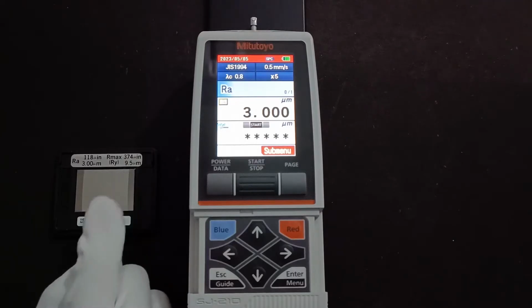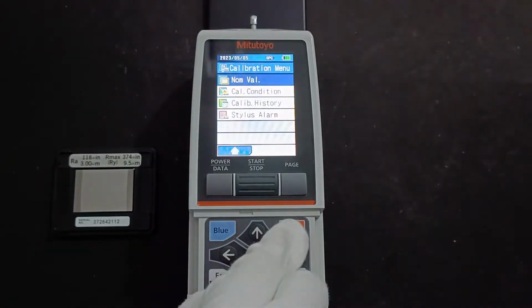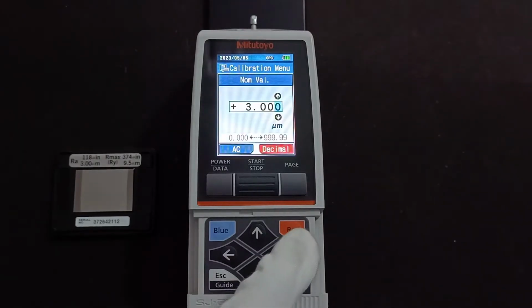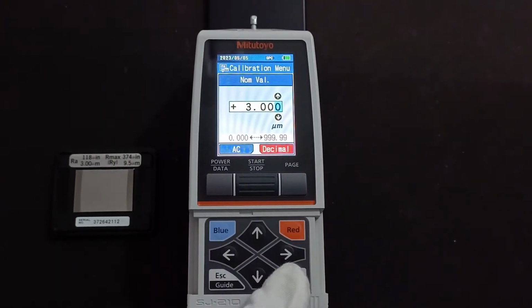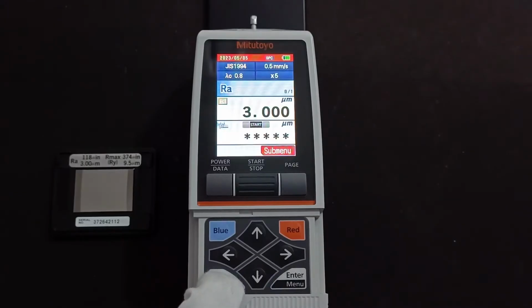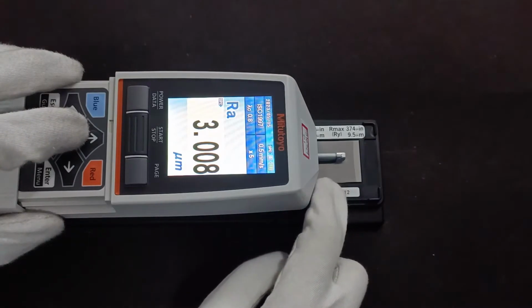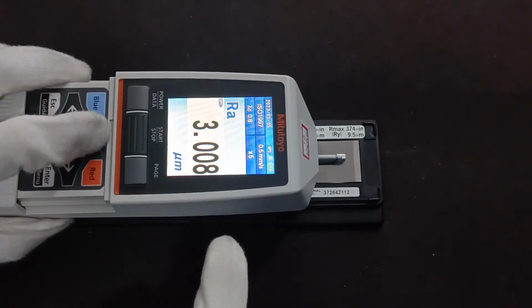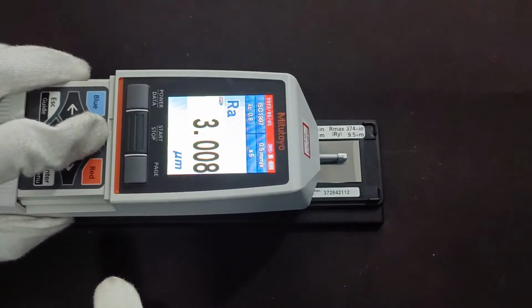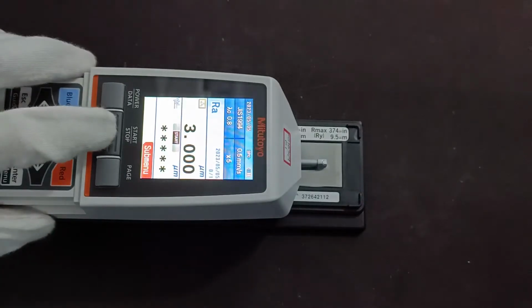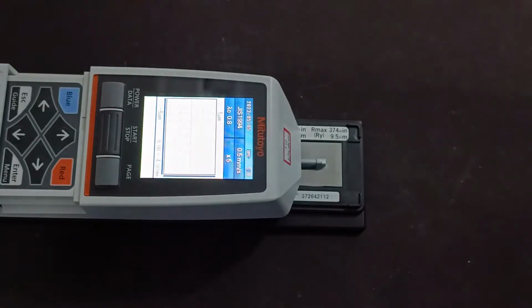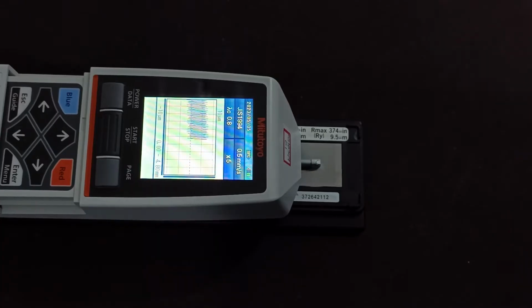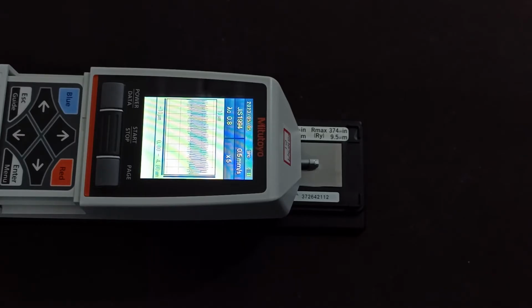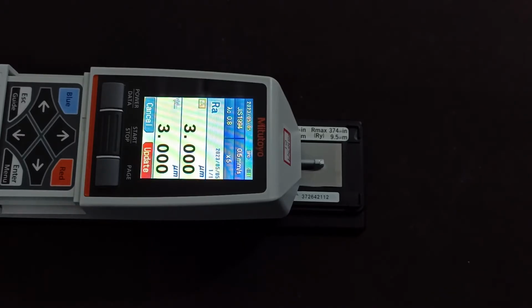or 374 micro inches. With respect to the Ra value, let's set the value in our device. Increase or decrease if required. Now let's calibrate this specimen. These are the lay lines. These lines should be perpendicular to the tracing direction. While placing the probe in the correct position, the red light turns blue. Now let's press the start button. The specimen is getting traced. The calibrated value should be plus or minus 0.05 microns. If the value is within the limit, press update.